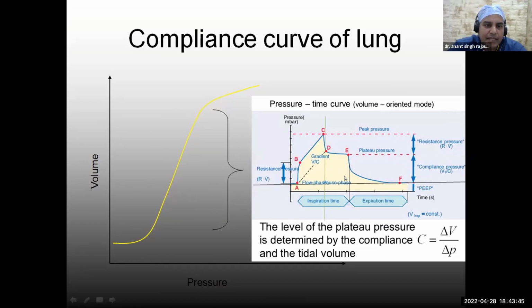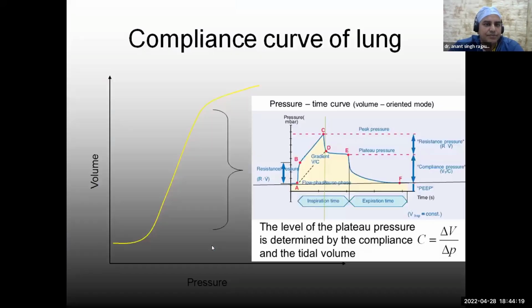This vertical green line that you can see indicates the active inspiration, where the flow is taking place from the ventilator to the patient. So the green line divides that phase. And after this green line, whatever is happening is because of the redistribution. There is no flow from the ventilator to the patient, but redistribution of the gases within the lung. And then from this point, expiration has begun. So we'll be seeing all these graphs again and again many times in subsequent slides.